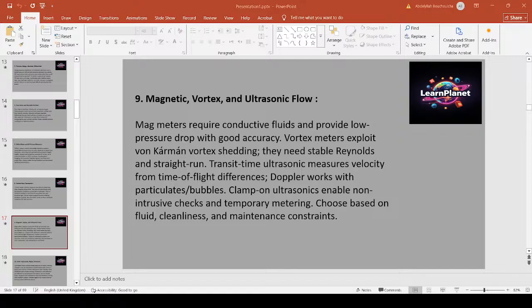Magmeters require conductive fluid. They offer near zero pressure drop and wide ranges for slurries. Vortex meters use vortex shedding and need stable Reynolds numbers with straight runs. Transit time ultrasonic time of flight works for clean fluids. Doppler ultrasonic works with entrained particles or bubbles. Clamp-on ultrasonic offers non-intrusive verification but typically lower accuracy than inline meters. Example: choose a magmeter for wastewater with solids. Use clamp-on ultrasonic for temporary verification during commissioning.